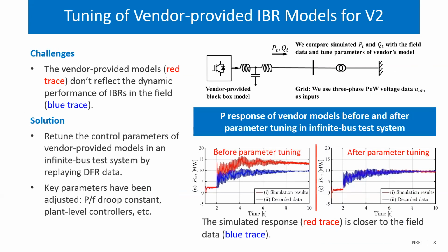So we tested it through a single infinite bus. We retuned the control parameters of the vendor-provided model by replaying the DFR data at the point of interconnection. This was a significant and important step, to make sure the model actually reflects the dynamic characteristics of the field devices.